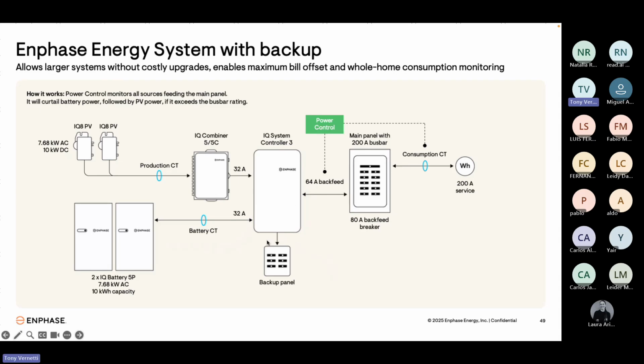Then here we have a backup panel, sometimes called the backup loads panel or essential loads panel. The loads that the homeowner needs backed up have to be relocated from the main service panel into this backup panel. Now, in some homes there already exists a separation, a sub panel maybe in the garage or a closet, that has those essential loads already in it. If that's the case, you can simply install the system controller between the main panel and that existing sub panel.